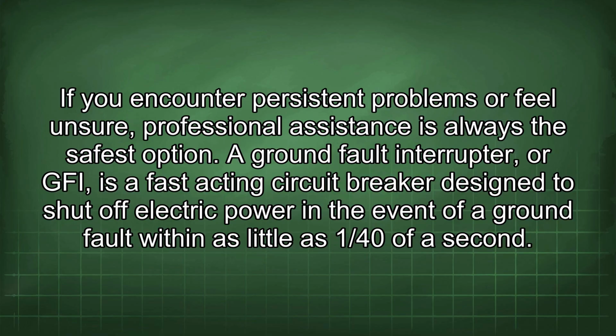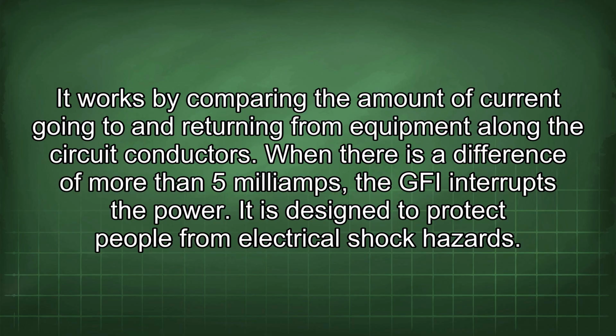The ground fault interrupter, or GFI, is a fast-acting circuit breaker designed to shut off electric power in the event of a ground fault within as little as 1/40 of a second. It works by comparing the amount of current going to and returning from equipment along the circuit conductors. When there is a difference of more than 5 milliamps, the GFI interrupts the power. It is designed to protect people from electrical shock hazards.